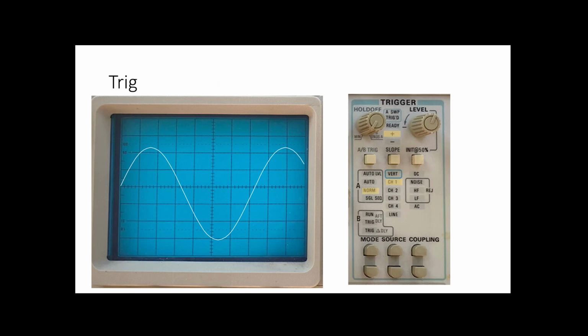If I put it to normal, then in normal mode, what happens is there's a level knob there. You see at the top right-hand side, level. And that level knob, it doesn't have a number on it. You can't set level 3 or level 7 or anything. You just have to twiddle it and see what you've got. And basically what that does is it picks the level on the left-hand side of the screen that the trace starts at. So now my trace, when it gets to the left-hand side of the screen, it will wait until it gets to that point right in the centre, and then it'll trigger. And when it comes back, it'll wait again, and then it'll trigger. And because it's always triggering at the same point on the screen, the traces always go over the top of each other. And so instead of the spirograph, I get the signal tidied up, always the same.